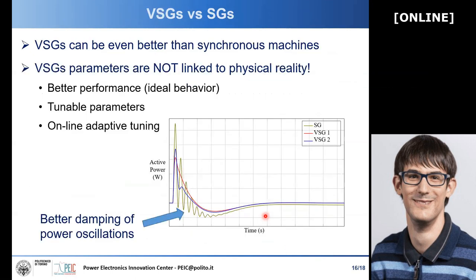This is not something we can do with real synchronous machines. This is why virtual synchronous machines can be even better than synchronous machines — they can feature better performance since we are dealing with an ideal model, not a real one. We have tunable parameters that we can change even online with adaptive tuning. For example, if the grid conditions change, we can change the parameters. As you can see here, the inertial behavior in yellow shows the behavior of a real synchronous generator with large power oscillations, which are undesirable. Virtual synchronous generators avoid this because the virtual model eliminates the causes of those oscillations.